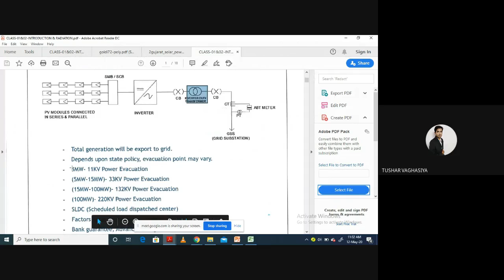If our power plant is up to 5 megawatt, then the power evacuation is at 11 kV. If our power plant is 5 megawatt to 15 megawatt, we can do power evacuation up to 33 kV. Same as that, for 15 to 100 megawatt, there is 132 kV. And if our power plant is more than 100 megawatt, then we have to evacuate our power to the 220 kV grid substation.